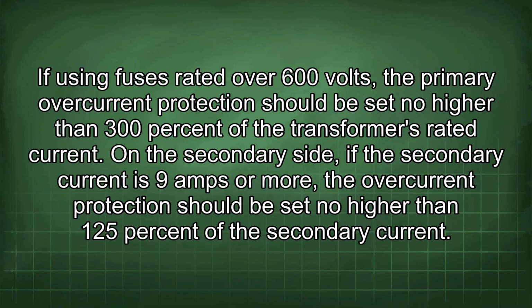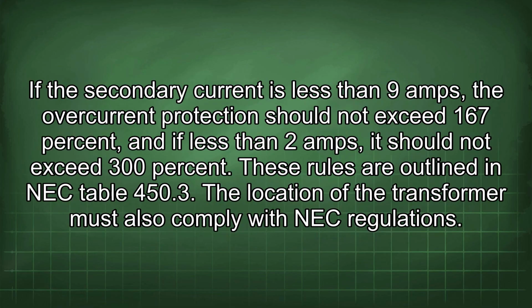be set no higher than 125% of the secondary current. If the secondary current is less than 9 amps, the overcurrent protection should not exceed 167%, and if less than 2 amps, it should not exceed 300%. These rules are outlined in NEC Table 450.3.